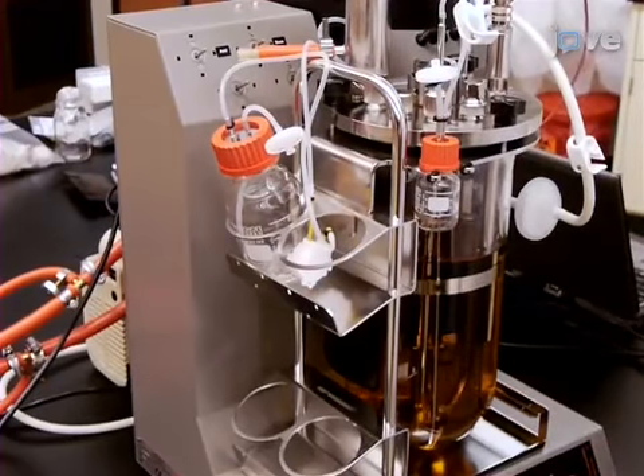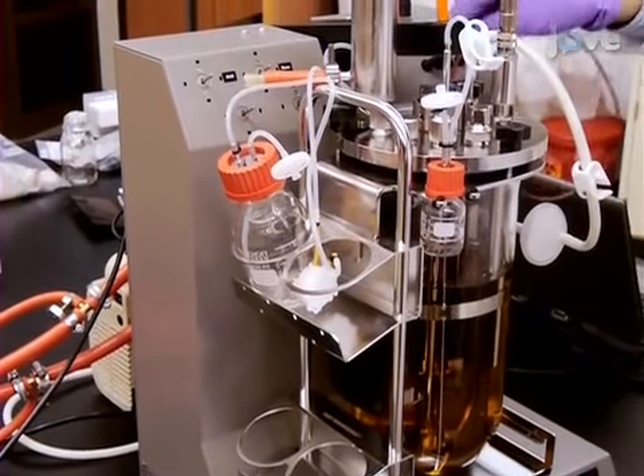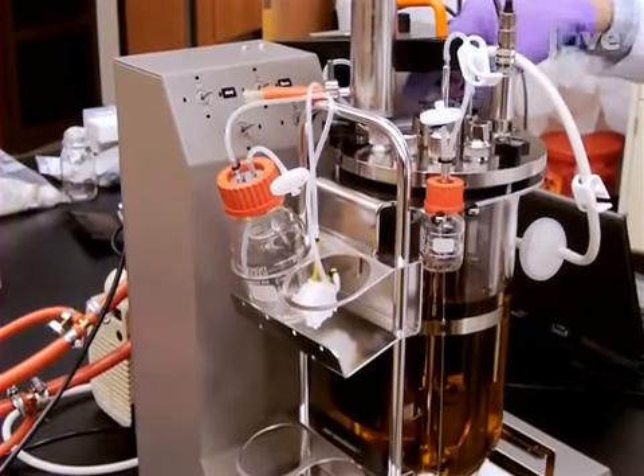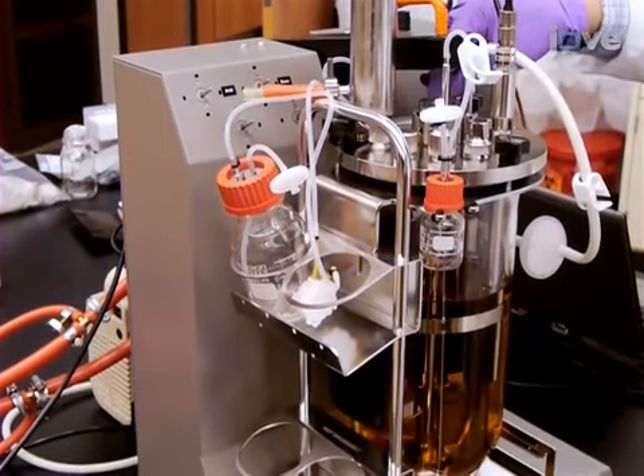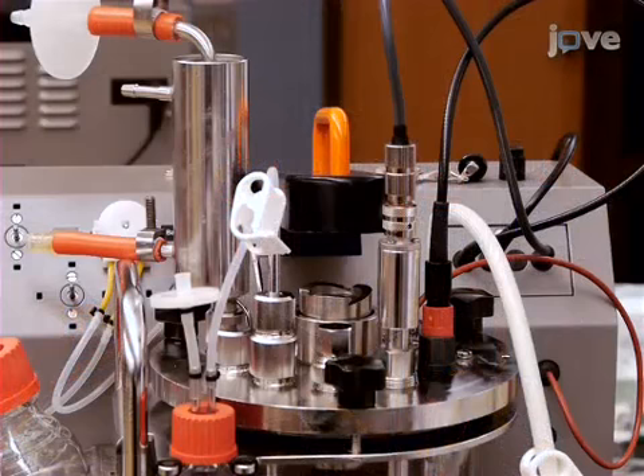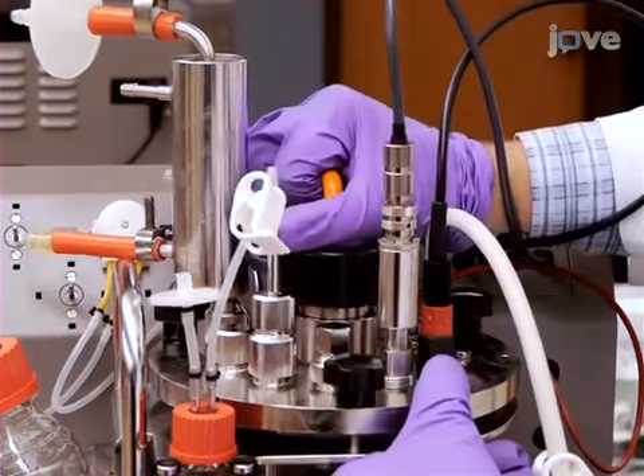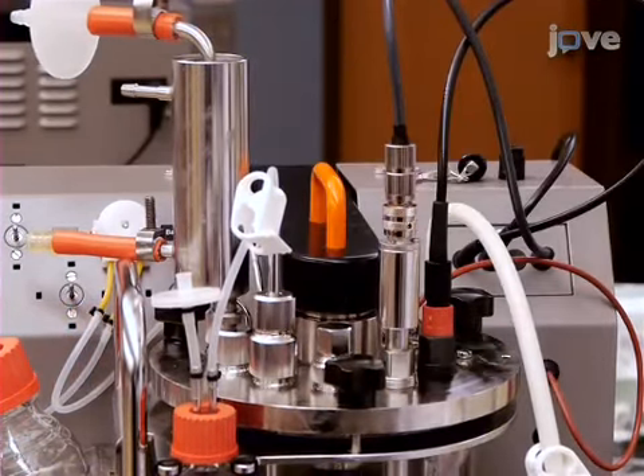Put the temperature sensor in the thermowell on the head plate. Ensure that it goes all the way to the bottom of the thermowell. Lower the agitation arm onto the vessel's impeller coupling.